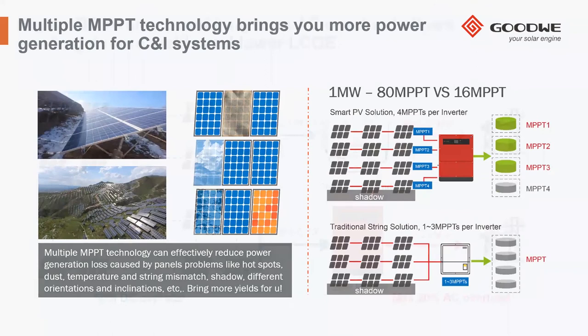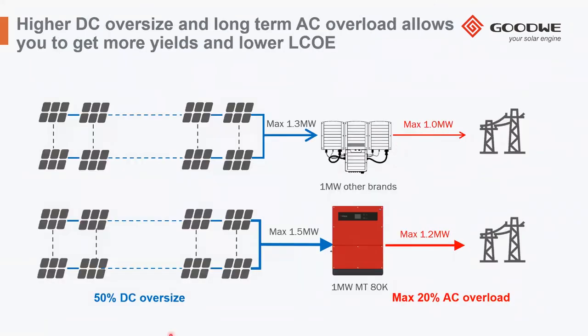Another interesting feature of our system is the capability to have up to 50% DC oversize and up to 20% AC overload. This is a big feature. Anytime you have to handle, let's say, requirements on the project where the grid owner imposes a maximum, as an example, of input on the DC side, or anytime you have to increase the power on the DC side to get, let's say, the AC output that you need.